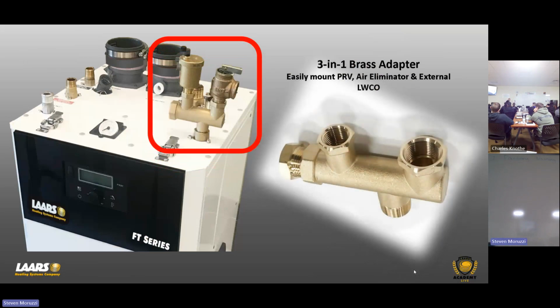And that's what it looks like. So you've got the 3-in-1. You've got one for your air elimination and relief valve. But you guys are required here to have an external low water cutoff, right? So this plug right here, not a test plug, this plug can be removed or not installed, and you can put your low water cutoff right here and then wire it back up to your terminal strip, okay? So that's all with the boiler right there.